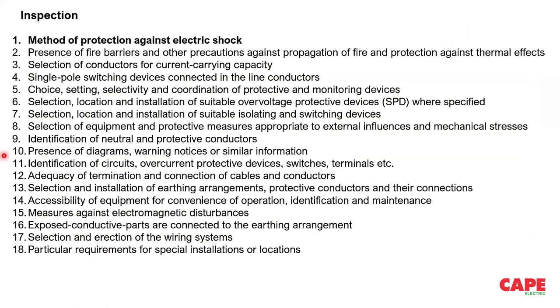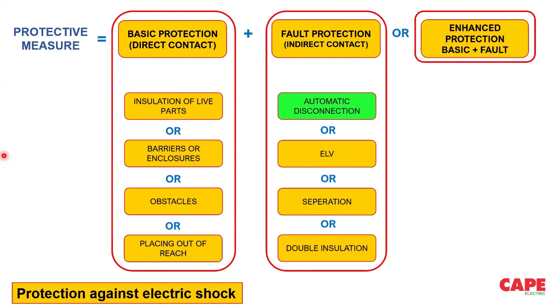In the last presentation, we discussed inspection and testing. There are 18 inspection points, and in the last presentation, we discussed the first inspection point, which is the method of protection against electric shock. There are several methods. There are several protective measures applicable for basic protection. You can see here on the left side, basic protection plus fault protection. Both are necessary in an electrical installation.